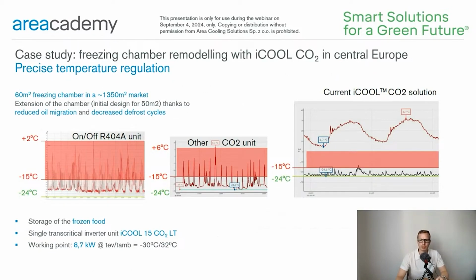Another case study relates to precise temperature control in the around 60 square meter freezing chamber in Europe, with the desired set point minus 24 degrees Celsius. In the beginning, the installation was supplied by an on-off solution with the 404A refrigerant. The critical temperature, minus 15 degrees Celsius, was exceeded too many times, as you can see here on the graph on the left. There were some moments when the temperature even reached plus 2 degrees Celsius.